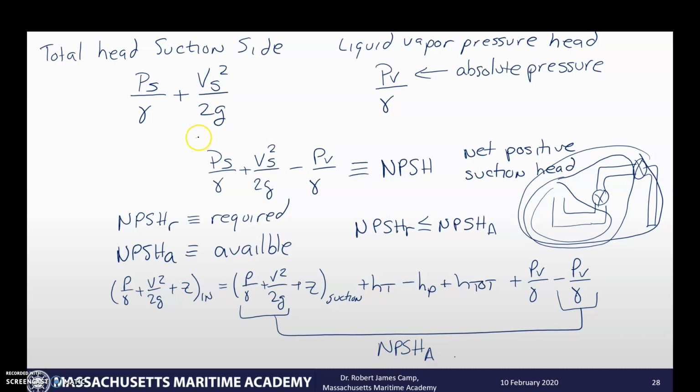So the important thing to remember here, though, is we're going to do this for every single pump in the system. Now, typically, in this class, we'll only be calculating out one, but it just means that we're spooling up a second control volume. So you'll see on a couple of these examples, we have a big piping system. We're going to have two control volumes because we need one specifically to find the net positive suction head available. And as long as we have more available in our system than what's required by the pump, we should be fine without any problems with cavitation.